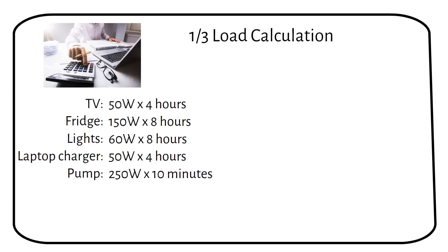Remember to add the inverter's idle consumption. Depending on the model, this can be 10 watts for a 500 watt inverter and up to 30 watts for 5 kilowatt inverters. The runtime will be 24 hours unless you turn it off at night.